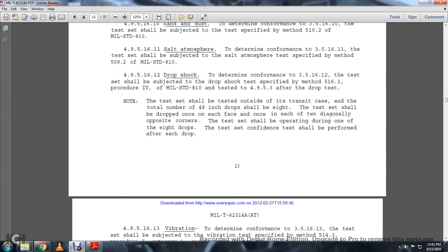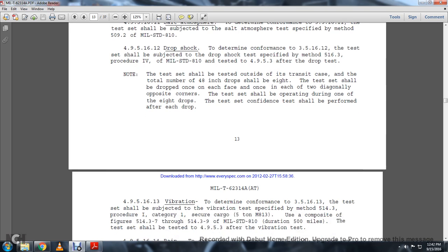Note, the test set shall be tested outside of the transit case, but the total number of the 48 inches drops shall be 8. The test set shall be dropped one to each of the faces, and one each of the two diagonally opposite corners. This shall be operating during one of the 8 drops. The test set confidence test shall be performed after each drop.